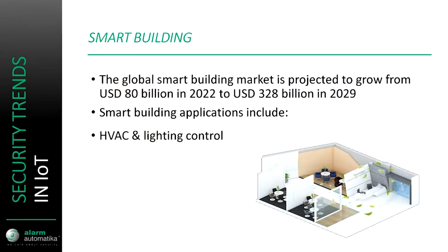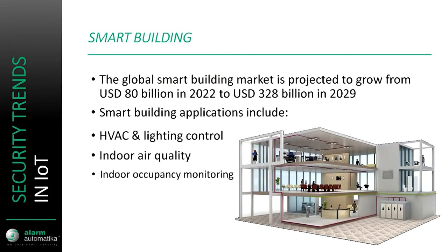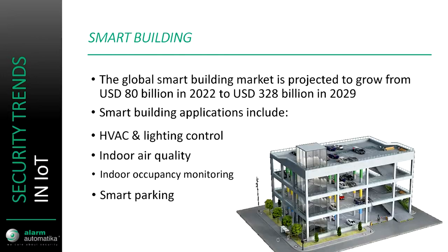Smart building and smart city technologies can be used within a building to control lighting, heating, and AC. They can monitor air quality — for example, in classrooms, if windows are closed too long, children lose concentration, become irritable, and it gets hot. These sensors can be connected with ventilation systems, or at minimum give an alarm when there's too much CO2 in the air. During the pandemic, and still today, indoor occupancy monitoring with integration with lighting or heating allows a building to automatically turn off lights and reduce temperature when a floor is empty in the evening.